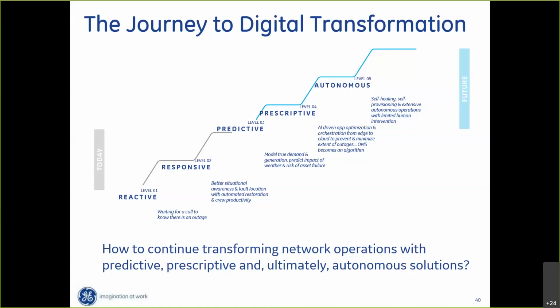So utilities can implement this logic in 3 different ways. You can implement the logic and have it give you recommendations, but a human is always in the loop to implement the recommendations. That's called the manual way of control. Second would be semi-automatic. A lot of utilities are semi-automatic, where upstream restoration is done automatically, but they still keep a human in the loop for downstream. Upstream is very straightforward. Downstream can be more complicated if there's a number of normally open tie switches where the feeders can shift load segments from feeder to feeder and substation to substation.